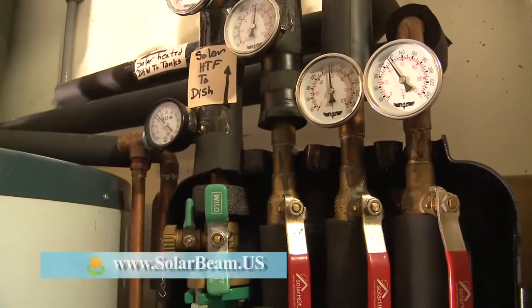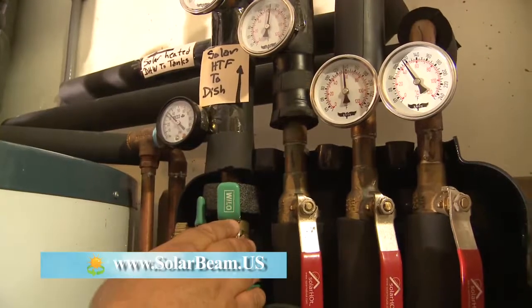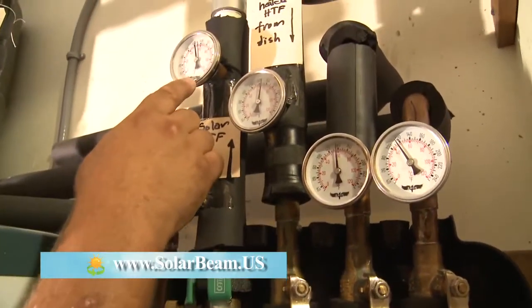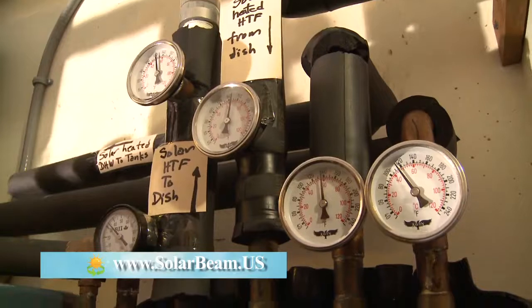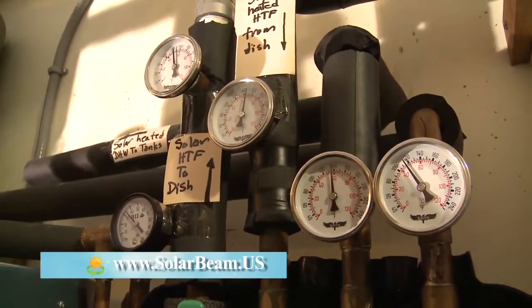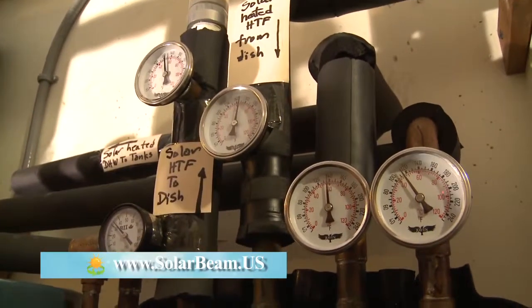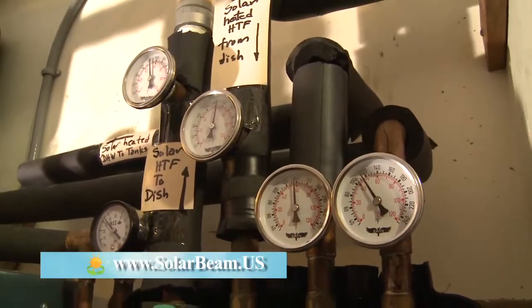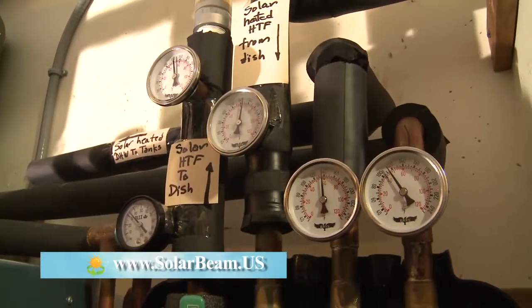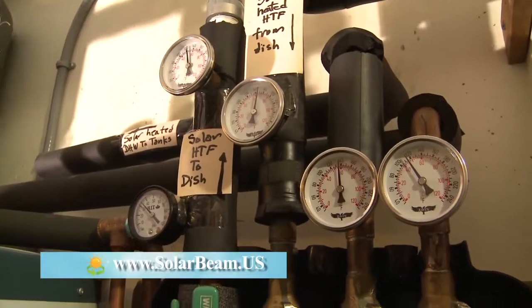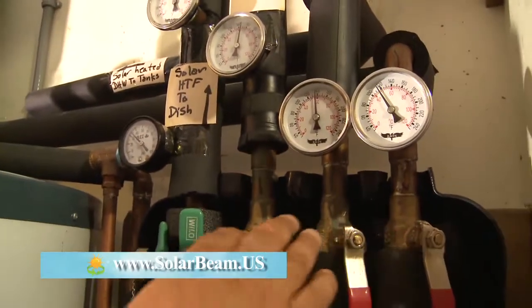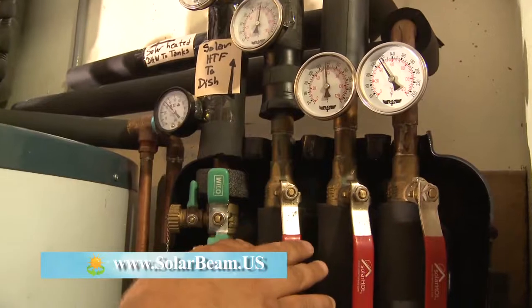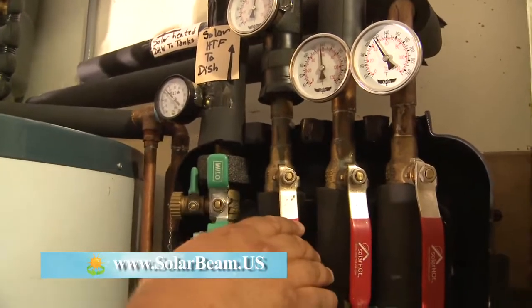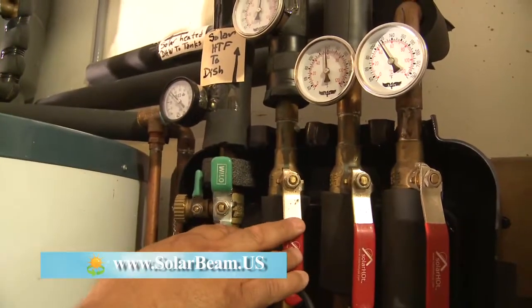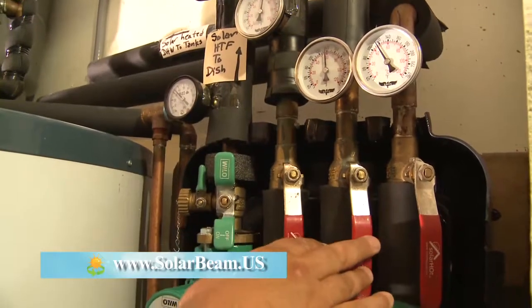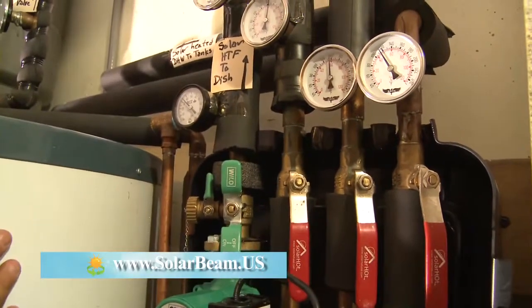I explained what the temperature difference was going to and from the SolarBeam. It's 125 degrees, it shows right here, of the temperature going out there. The returning temperature, as evidenced by this temperature gauge, is 150 degrees, and I'm giving everything in Fahrenheit because most people in America understand Fahrenheit. This other loop right here, there's a heat exchanger built into this pump station, and the heat exchanger extracts the heat from that's being created outside and stores it in the various tanks that I have in the home.